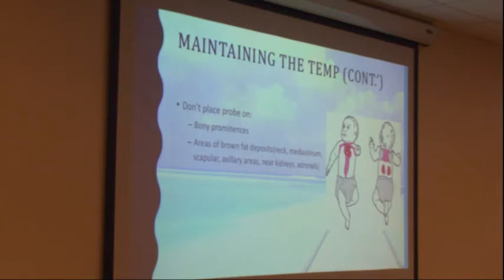Basically, brown fat deposits are areas with fast, high metabolism of adipose tissue. So those areas could be warmer than the rest of the body and give you false information. If you put your probe on those areas, it could send the wrong information to the radiant warmer, which will lead to cooling the baby and the baby becoming cold.